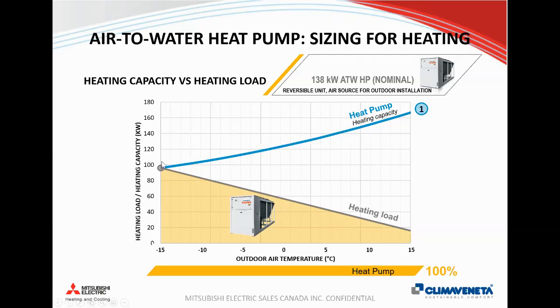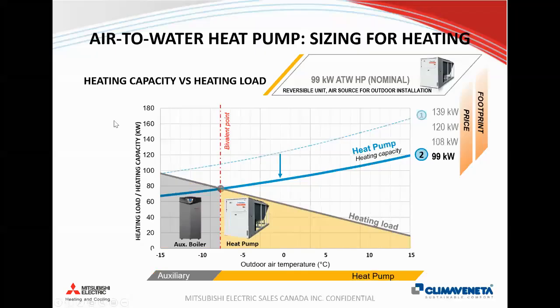But in this example, this would be selecting the heat pump to provide heat to the building at minus 15. So again, with a 35 degree or 40 degree Celsius supply, you can select the heat pump to meet 100% of the design capacity at minus 15. In reality, for Toronto, this line would extend to minus 23 or so with a higher heat load. So generally, if you're looking at how to optimize the size, you can look into the detailed specs of the equipment that you're considering to see how the COP will change according to outside air temperature and how the capacity will change according to outside air temperature. And in most cases, what you'll find, even though we can run the heat pump down to minus 15, chances are we'll probably want to switch over at a different outside air temperature, either because the COP is too low, or because of operating costs for an auxiliary gas boiler over a heat pump. It's all subjective and it's all part of the design.